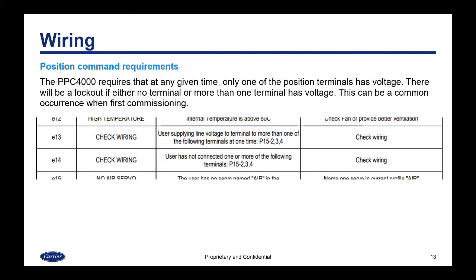The PPC4000 requires that at any given time, only one of the position terminals has voltage. There will be a lockout if either no terminal or more than one terminal has voltage. This can be a common occurrence when first commissioning; you will run into this lockout. In this particular case, E13, you'll get a lockout, check wiring, and it will tell you that there is voltage on more than one terminal, or E14 tells you there is no voltage.